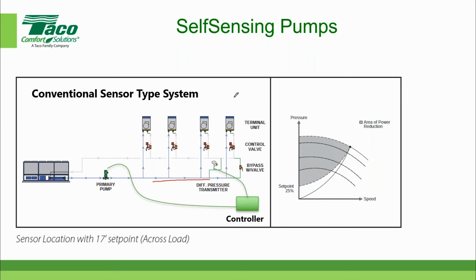And at the design flow, let's just make up a number and say we need 10 gallons per minute at this terminal device. And we would calculate what the pressure drop would be for each one of those 5 major components. And that would be the pressure that we're trying to maintain at the most remote point with our differential pressure transmitter. Hopefully that answered that question.